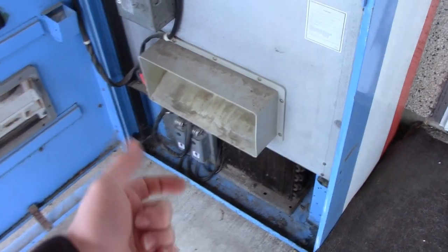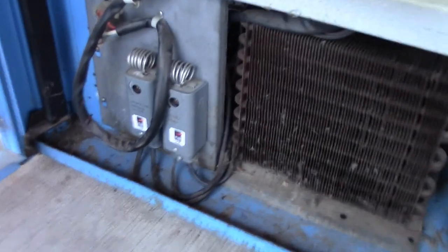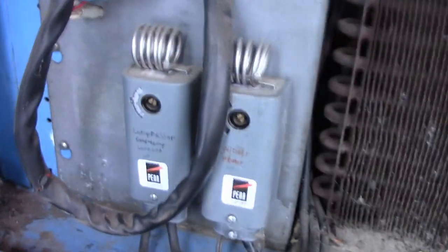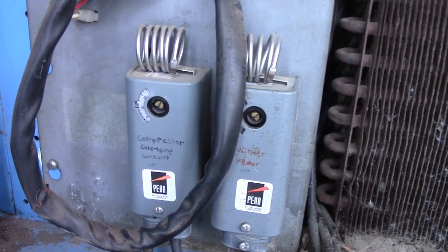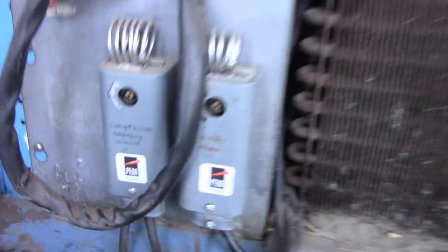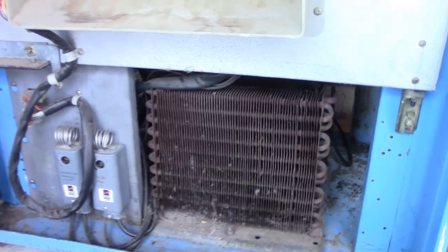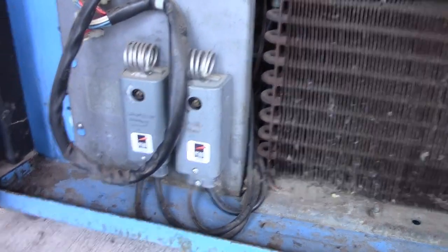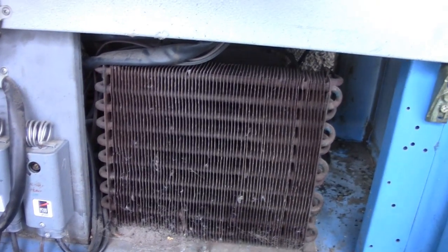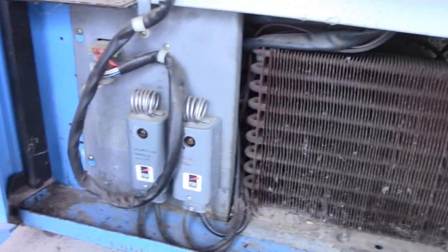Even though it's so cold outside, it really doesn't need to be running the compressor. We don't want to put that extra stress onto the compressor. Your oil thickens up, you've got to remove refrigerant in such a cooler situation, and it's just not going to work as efficiently — plus it wastes energy. So you'll notice down here I have these two controllers. One of them says 'compressor cold temperature lockout' and it's labeled for 30 degrees Fahrenheit.